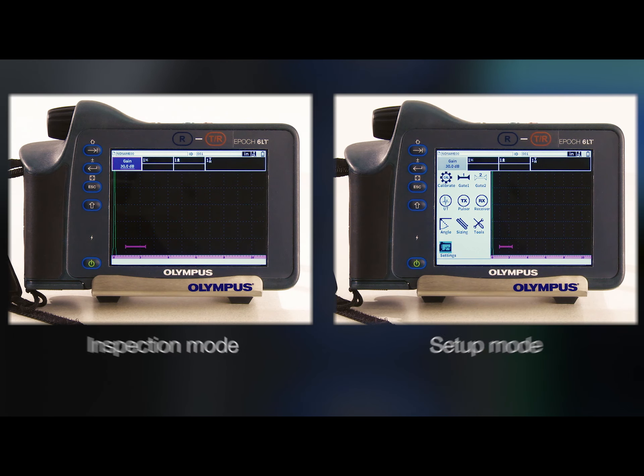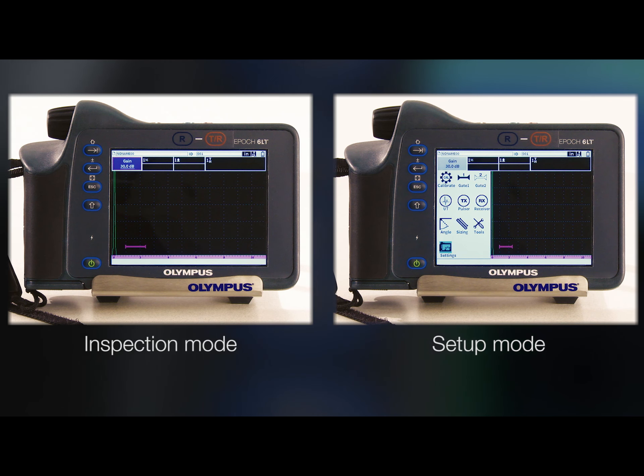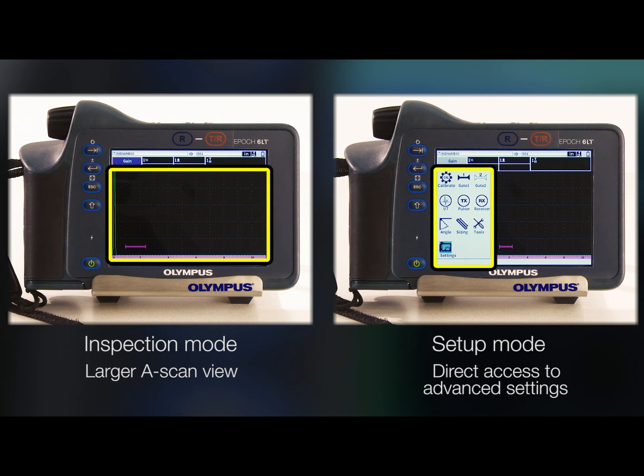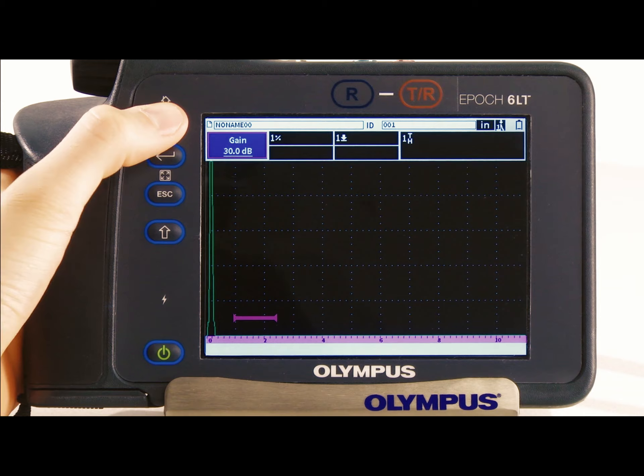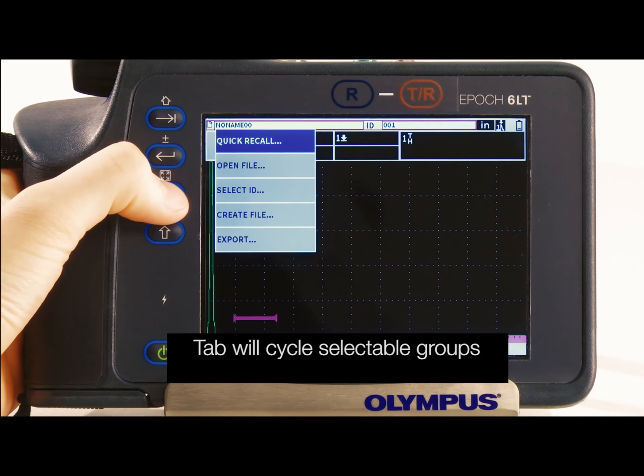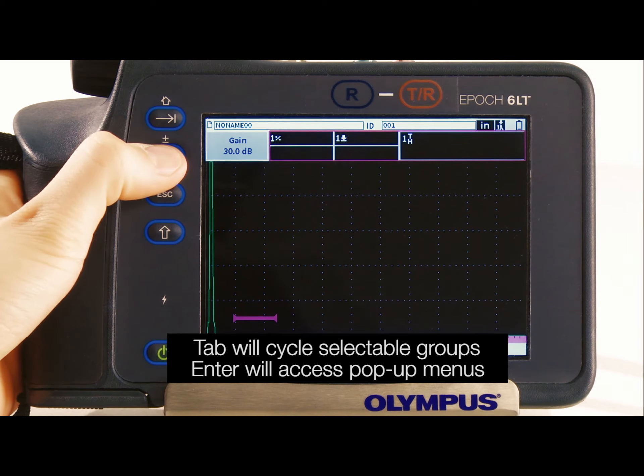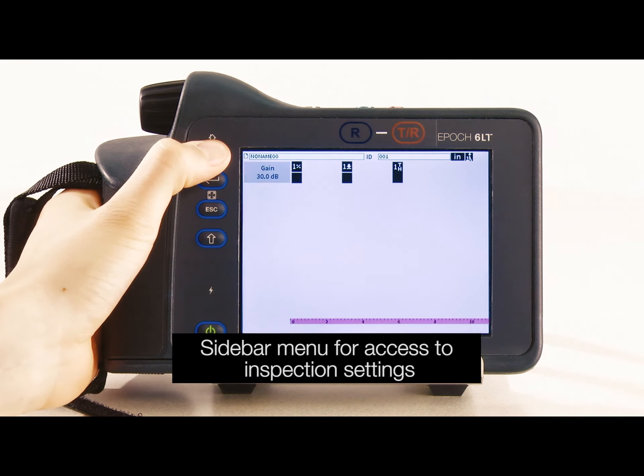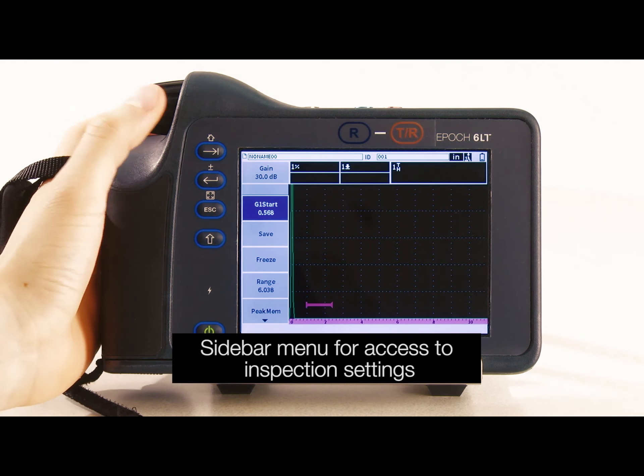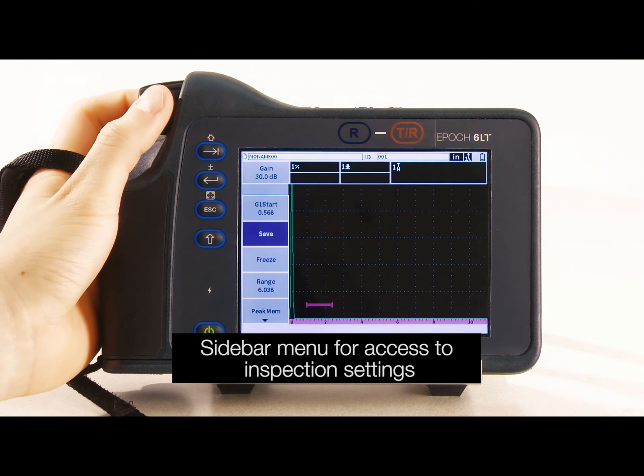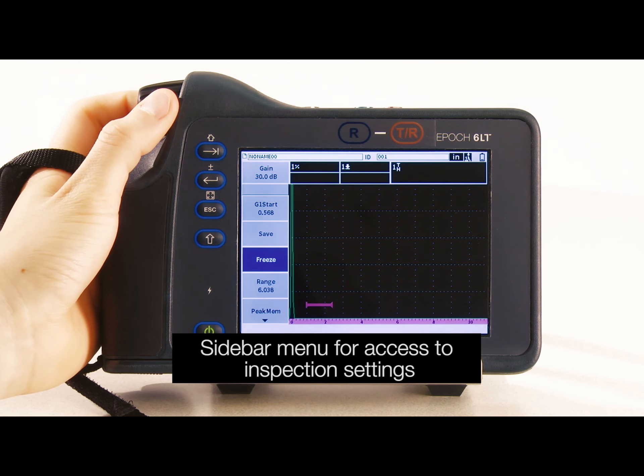The layout of inspection mode is similar to setup mode. The fundamental difference is a larger A-scan view instead of direct access to more advanced settings. Both modes operate similarly — press tab to cycle through the different selectable groups and press enter to access the respective pop-up menus. Instead of the icon menu, there is a sidebar menu granting access to necessary inspection settings, such as gate 1 start, save, and freeze, among others.